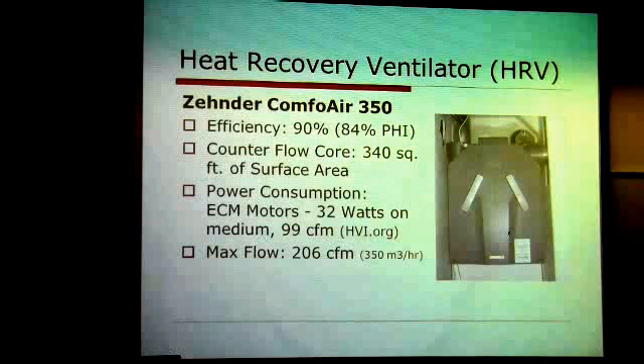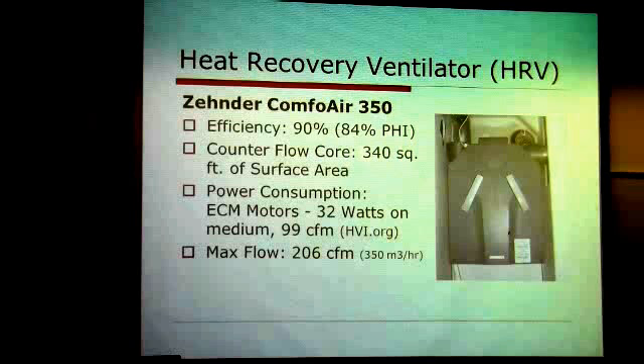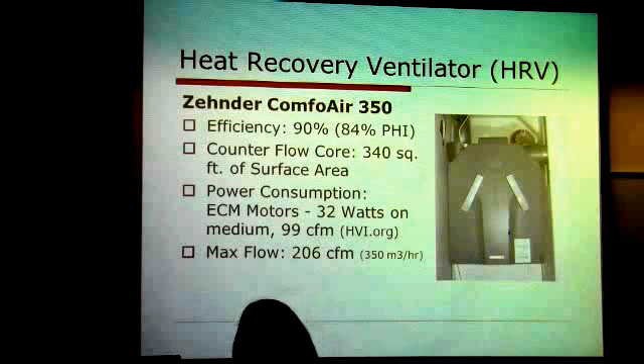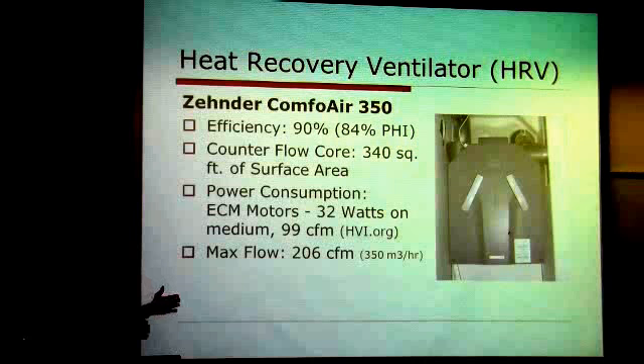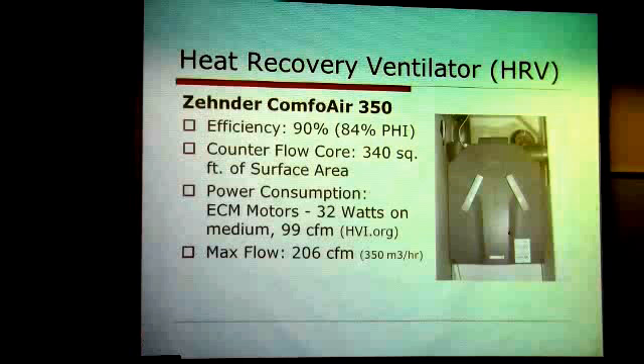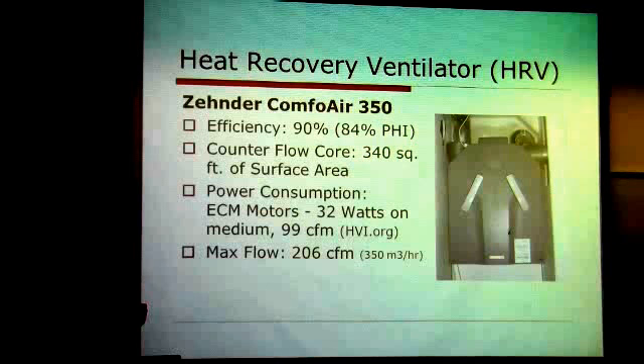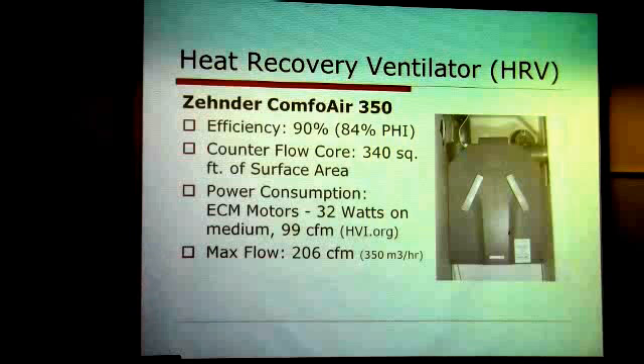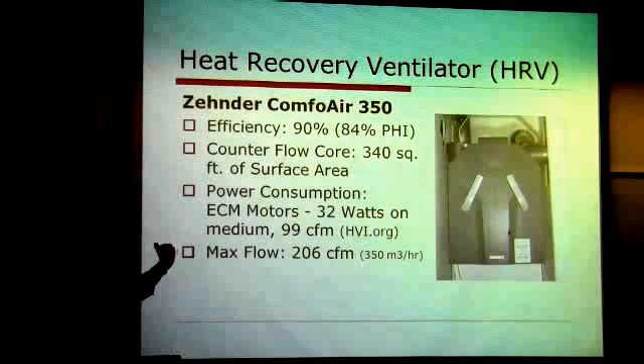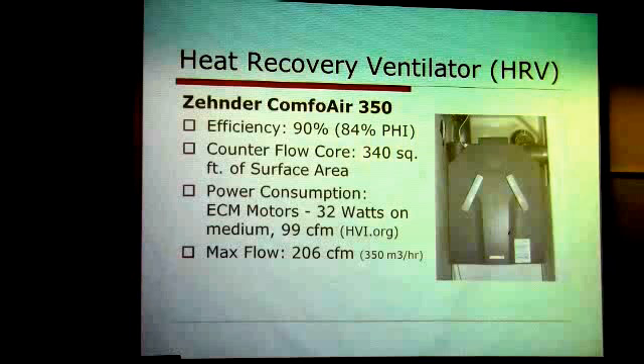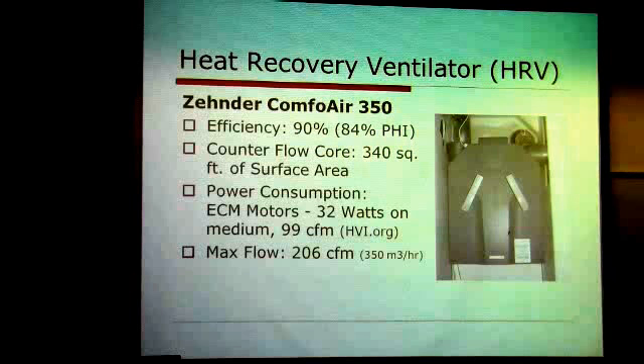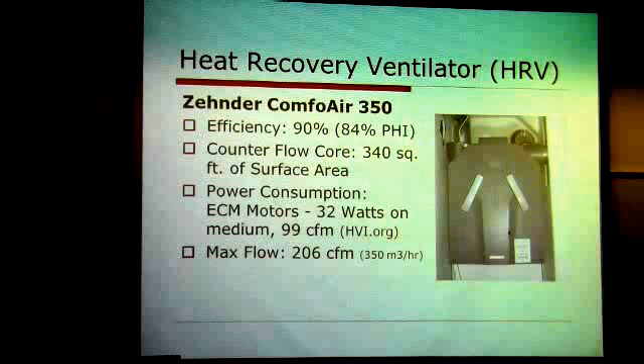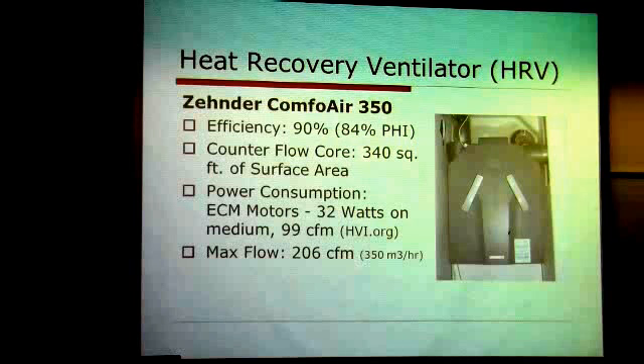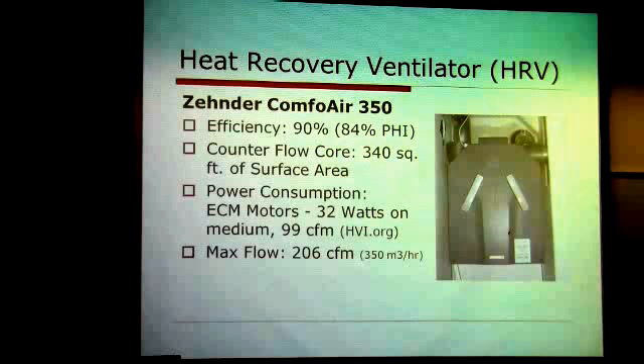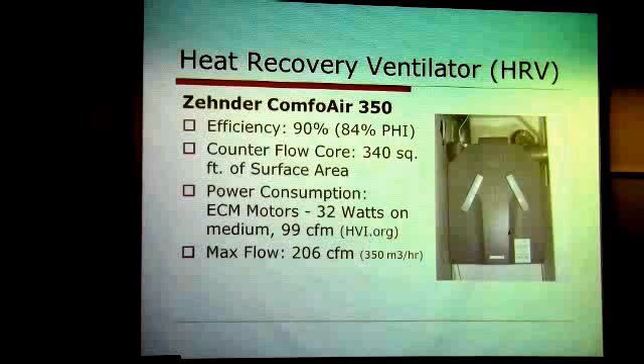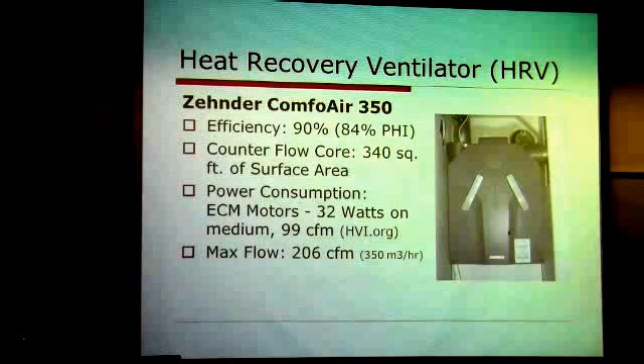Do these operate differently in heating season and cooling season? Is there a changeover, or does it do the same thing the whole year? It does the same thing. They don't change any of the ducting or passages inside. The air just comes in and passes. So if instead of coming in really cold and the other one transferring heat to it, it's coming in hot, say 95 degrees, and you're exhausting at 70, 72 degrees, that 95 degree temperature will reduce to within 2 or 3 degrees above room temperature, so it'll be coming in at 75 instead of 95. There are no changes to the system, and it just does that. Only air to air. Right.